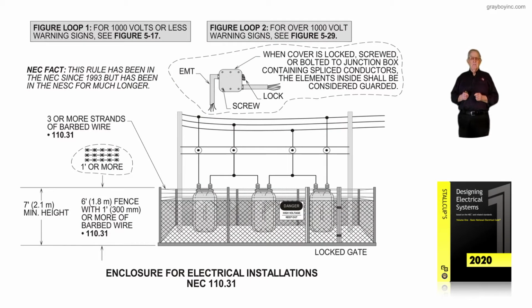Now, this illustration deals with enclosures for electrical installations in accordance with 110.31 of the code. Notice we have a substation illustrated. The main thing that has to be done here: who owns it? Is it a utility substation that would fall under, I believe, Chapter 1 of the National Electrical Safety Code?